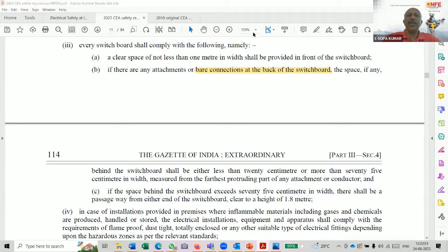Sir, okay, one thing, Gopal, I would like to add. In our NEC Part 1, Section 22, which speaks about electrical safety, we have given the arc flash distances, clearances, restricted area, prohibited area; we have clarified what the distances are. And that is as per the arc flash hazard assessment. So whatever they have mentioned here, 1 meter or 20 centimeters, that doesn't correlate with the requirements we have given in NEC Part 1, Section 22. So this regulation should be reviewed from that point also.